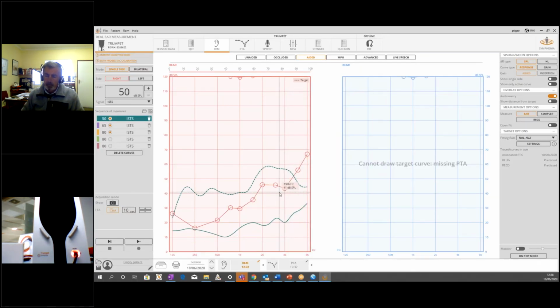Okay, and that's it. And then you have to perform this test, always using a speech signal for the medium sound and the highest one. It is very important, as I underlined before, to use the on-top mode, because with the on-top mode you can use two different software at the same time. Maestro software, in order to check the differences between the curve acquired for the patient under test and the target one. And the software of the hearing aid, because from that software you can adjust the gain, okay?